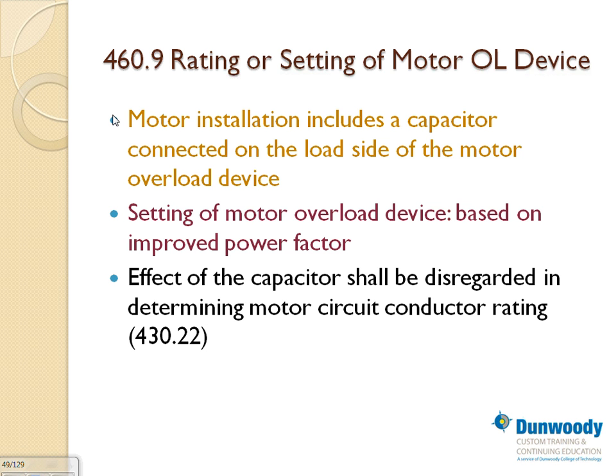Every time you energize the loads, you can either maintain them on at all times, or you can control part of them to go on and off based on the load or the voltage drop. The best way is to go down to the offenders and have a bank of capacitors right next to them. For example, when we did wastewater treatment plants, for every 30 horsepower motor or more, we specified a capacitor bank right next to it at the top of the MCC. When the motor turns on, the capacitor turns on and mitigates the power factor. The motor pulls the power factor down, the capacitor pulls it up, so there's no effect on the power system.